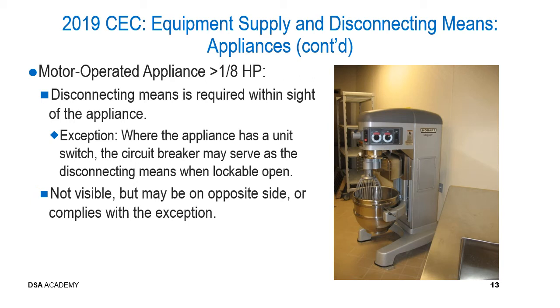Okay? Now, just because you don't see a disconnect in this particular picture does not mean that it doesn't exist. It is certainly possible that the disconnecting means is on the other side of this piece of equipment, and we don't know that. Or it could certainly comply with the exception. So again, the information to take from these exceptions and from the generalized rule of the disconnect required within sight from the appliance or the equipment is that you need to inspect per the plans. The plans are going to give you the information that has been approved by the design team, and you can rest assured that their design and their recommendations for construction comply with the current applicable California Electrical Code.